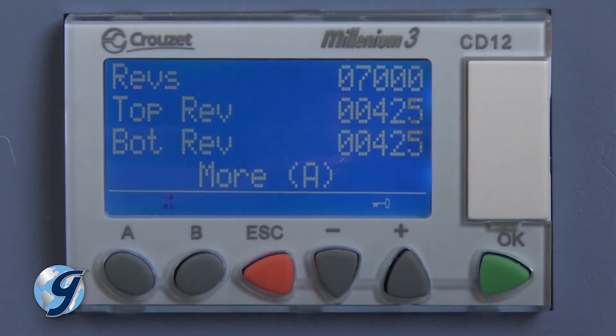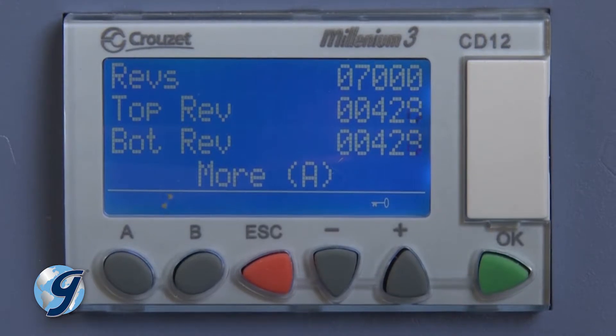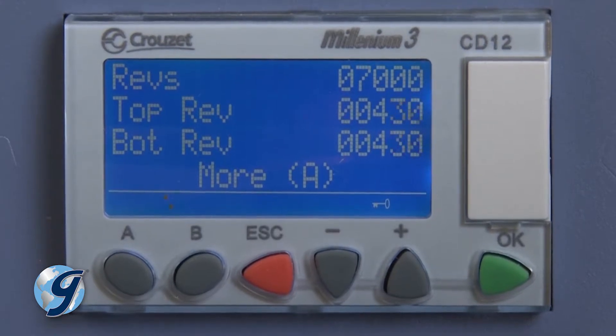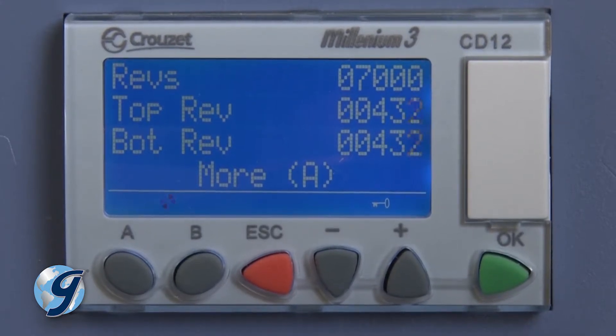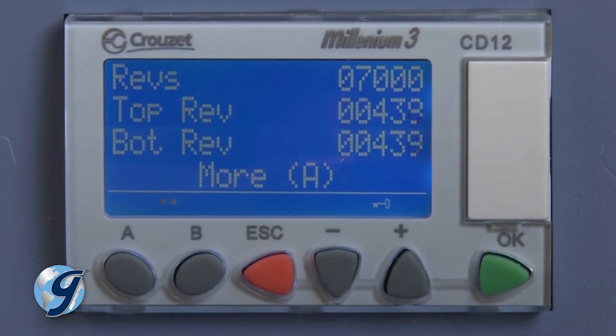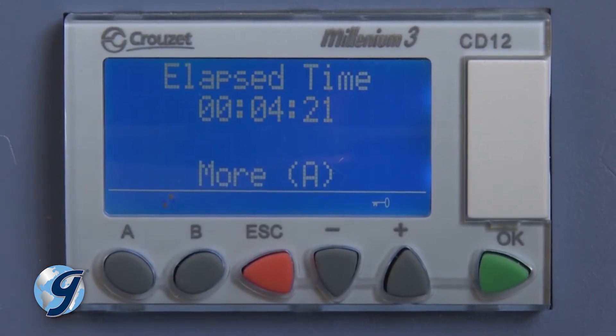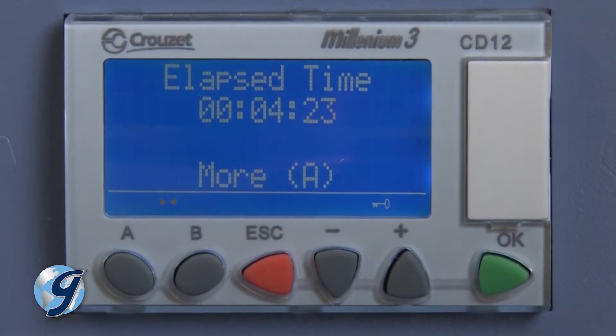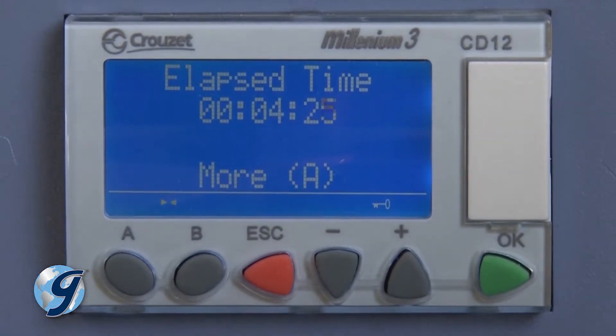In the revolutions mode, once the counter is set to a specific number of revolutions, the test will run until the revolutions counter reaches a set point. Elapsed time can be displayed in the revolutions mode, but does not control the test.